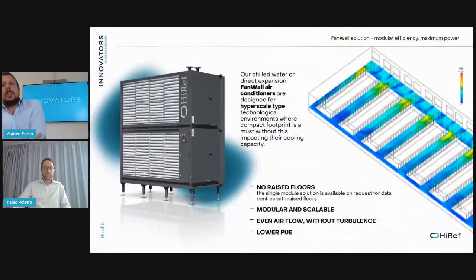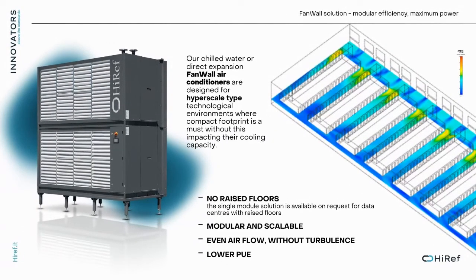Then what is really interesting to talk about is a new type of unit that is taking more and more place in the cooling distribution, that is the fan wall. In this case, the fan wall is substituting, let me say, a wall of the room that becomes an active wall. So it means that from this wall we can distribute cold air directly into the room. All the room is flooded with this smooth cold air that is navigating through the racks. All the hot air is contained in the hot aisle containment, and then comes back through the double ceiling into the unit. I said double ceiling because this type of unit is designed for no raised floor data centers.